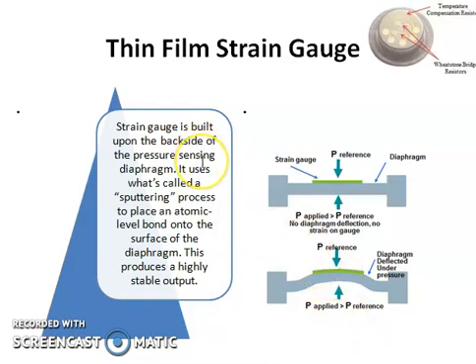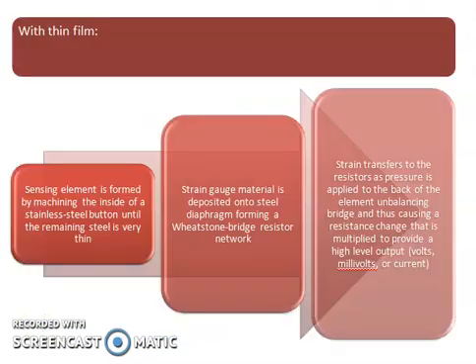The strain gauge is built upon the back side of the pressure sensing diaphragm. It uses what's called a sputtering process to place an atomic level bond onto the surface of the diaphragm. This produces a highly stable output. The sensing element is formed by machining the inside of a stainless steel button until the remaining steel is very thin. The strain gauge material is deposited onto the steel diaphragm, forming a Wheatstone bridge resistor network.